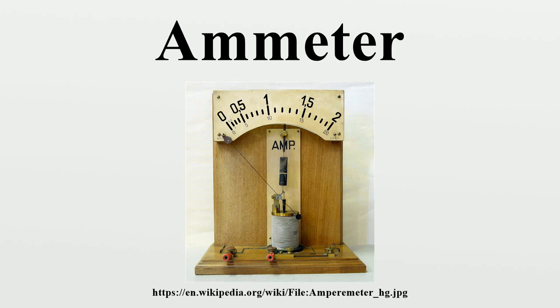This instrument can respond to both alternating and direct current and also indicates true RMS for AC. See wattmeter for an alternative use for this instrument. Moving iron ammeters use a piece of iron which moves when acted upon by the electromagnetic force of a fixed coil of wire. This type of meter responds to both direct and alternating currents. The iron element consists of a moving vane attached to a pointer, and a fixed vane, surrounded by a coil. As alternating or direct current flows through the coil and induces a magnetic field in both vanes, the vanes repel each other and the moving vane deflects against the restoring force provided by fine helical springs.